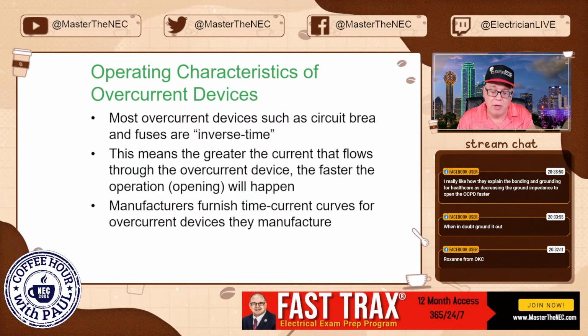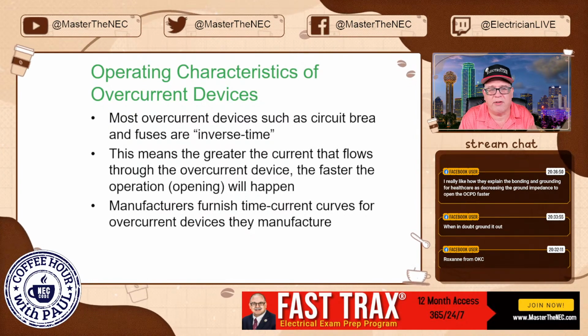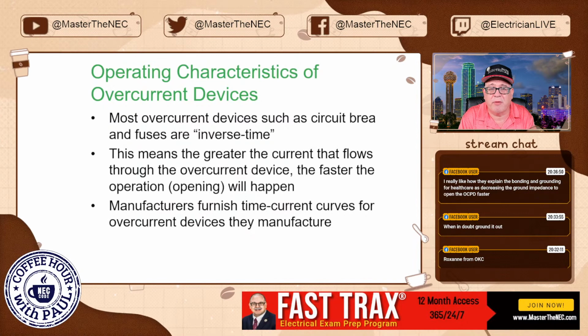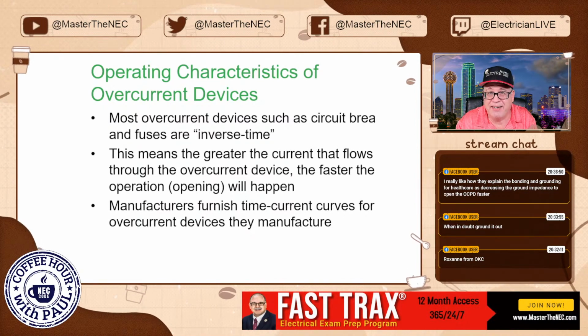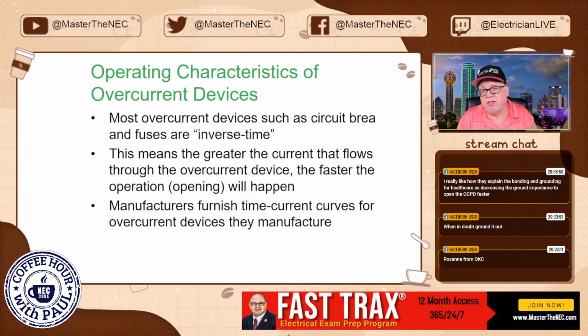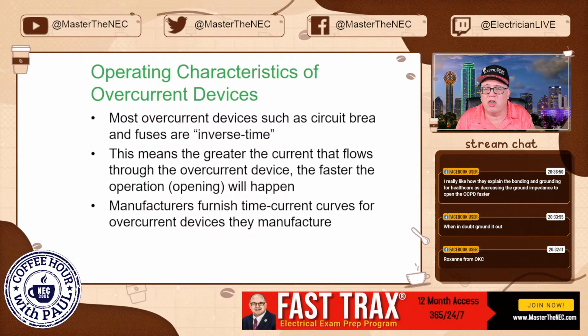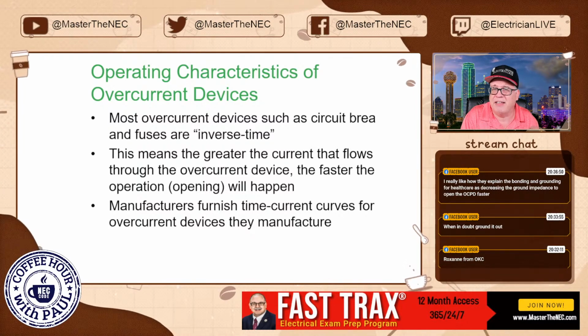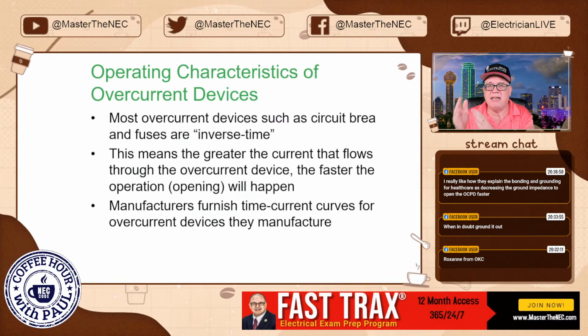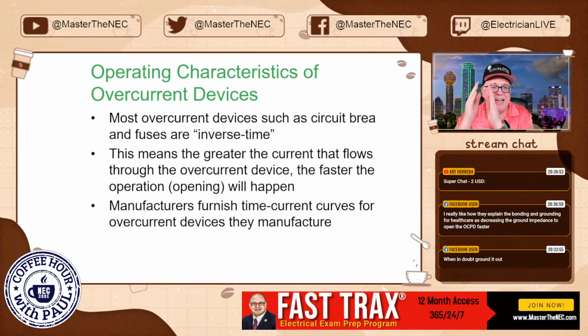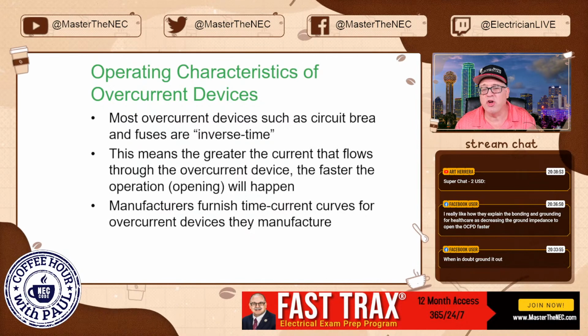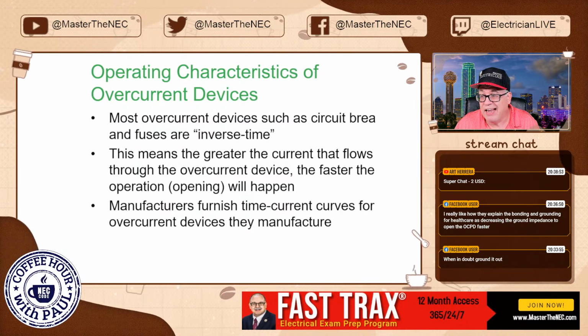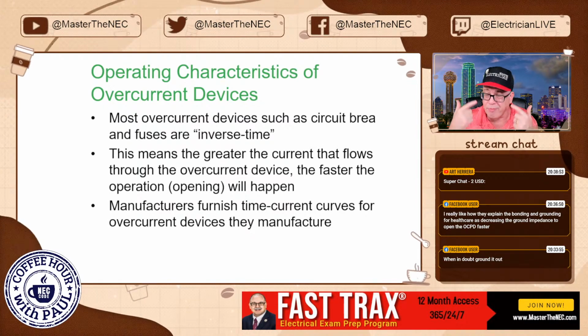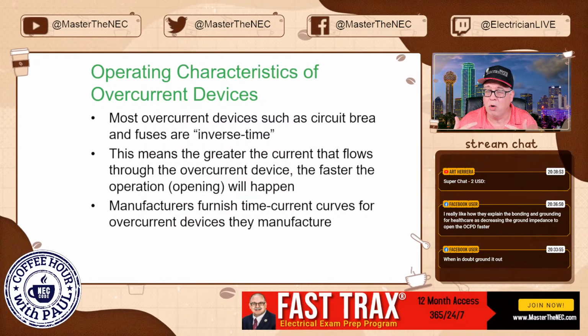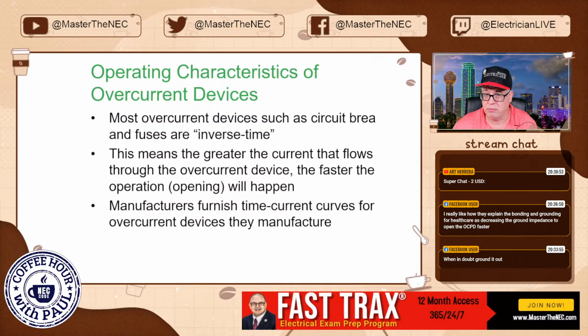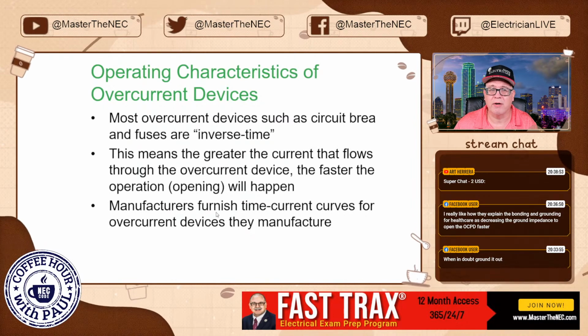Now, the good news is most of the manufacturers, if you go with the electrical contractor who is using something like a Schneider or Eaton, they're probably going to develop the entire system. So rather than you worrying about curves, they will usually look at this and tell you the equipment you need. And as long as you install it as they tell you to install it, then you're going to be selectively coordinated. And that's going to save you a lot. Don't let your brain start wandering around a trip curve when the manufacturers will do it for you. Okay? Work smarter, not harder.